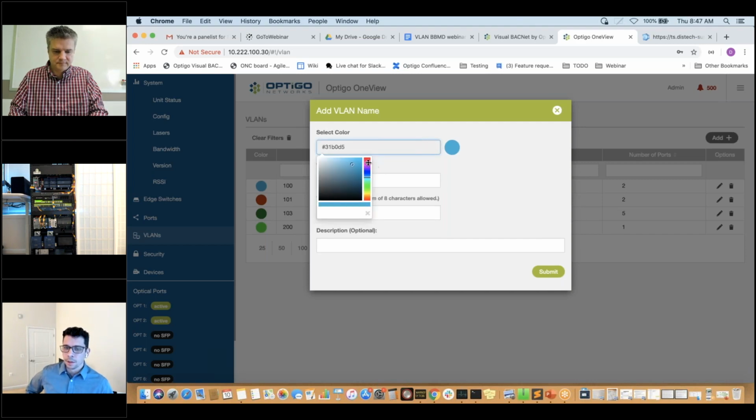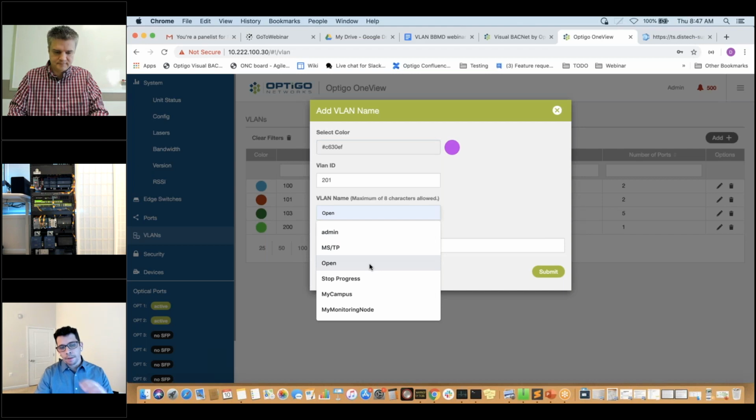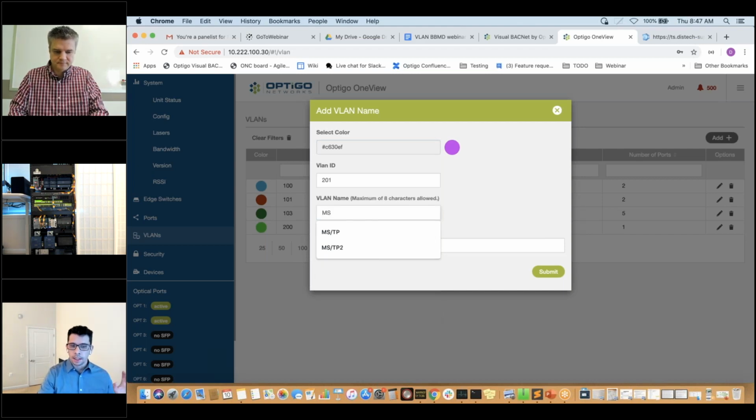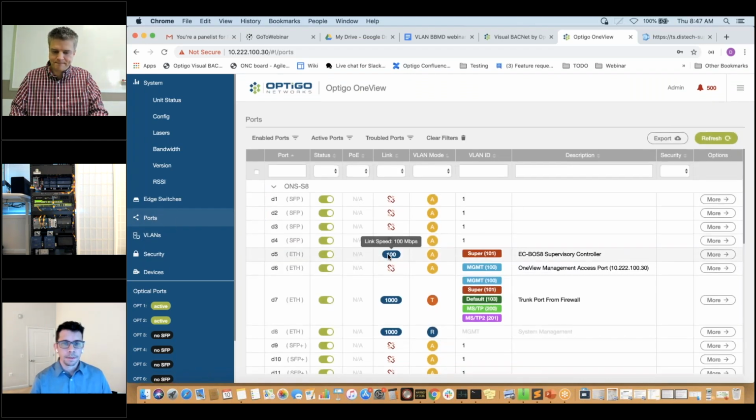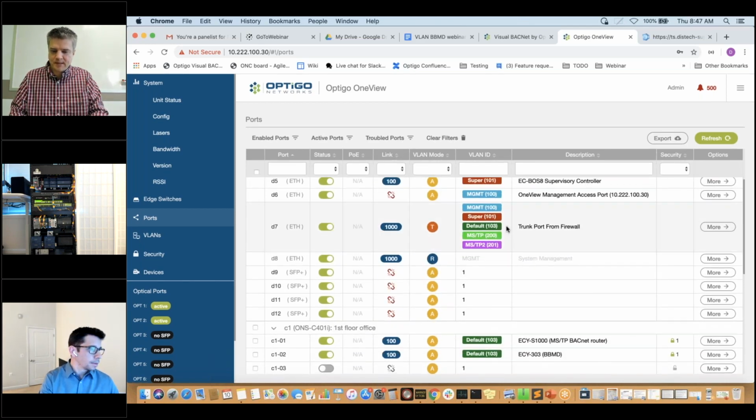So it's not always as easy. It's easy to say that. I know it's very difficult to do that in practice. But one of the ways I do that is if I have a system with a few VLANs, on every VLAN, I'll put every MAC address and I'll give every controller an assigned address if the range allows for it. So that way, if I move them around, I never have to go back in there and adjust it again. In large network ranges, that's not going to happen. But in a small site, it's very feasible to do that. And we'll talk about that here right before Dave. In fact, if Dave will switch to my screen, I'll bring that up for you real quick.